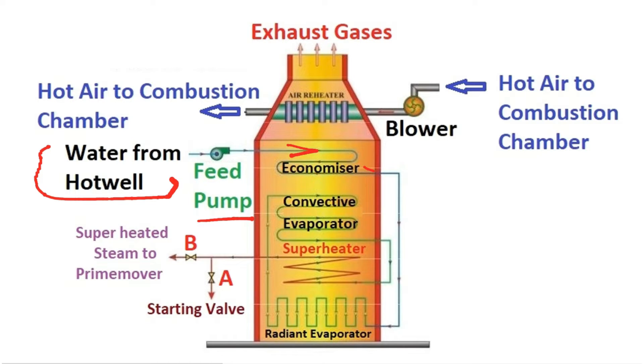Feed water from the feed pump — which is connected to the hot well, the outlet of the condenser — passes through the economizer and then through the radiant evaporator. In the radiant evaporator, as shown in the figure, the majority of the water is converted into steam. The remaining water is evaporated in the final evaporator by absorbing heat from hot gases by convection.